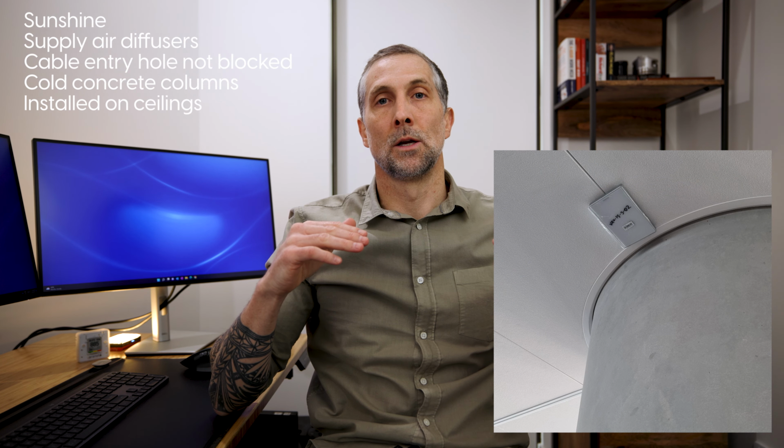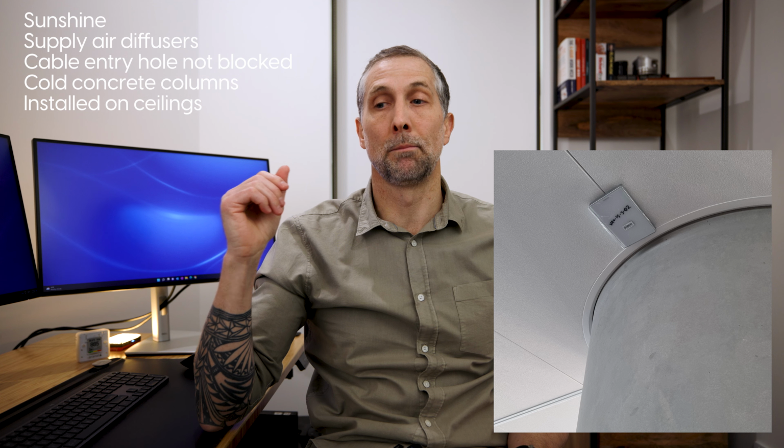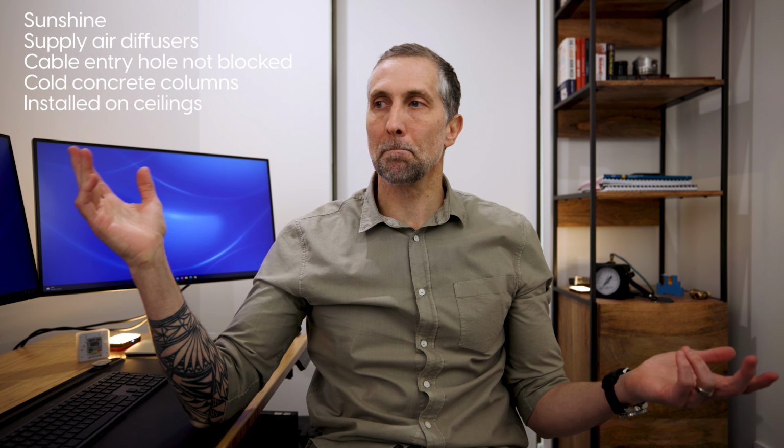Recently, last year at an inspection, I saw temperature sensors installed on the ceiling because there's a big open area and there wasn't walls and things. They had to put the sensor somewhere, so they're stuck on the ceiling. That is a very bad place to install a sensor. I reckon if you've got a 30 or 40 story commercial office, there's going to be 5 situations or more where the temperature sensor is rolled up in the ceiling, because through the years of doing fit out projects when they're moving walls around, the mechanical contractor may not have engaged the incumbent BMS company to do disconnects, reconnects, relocates. They just use their mechanical electricians. So sometimes the sensor is rolled up in the ceiling still.